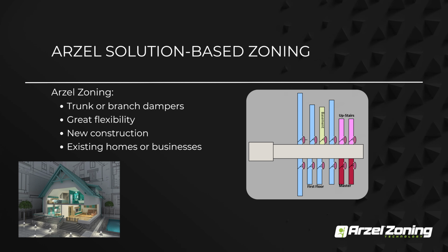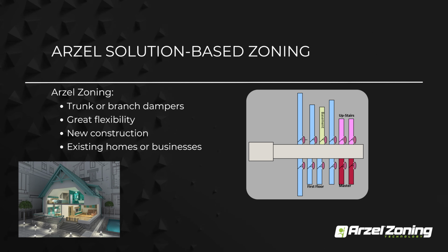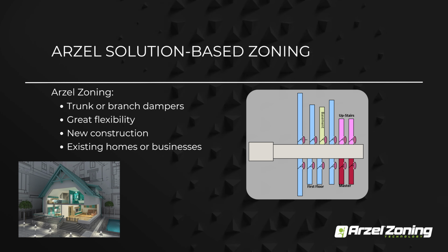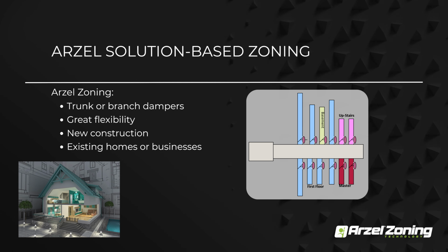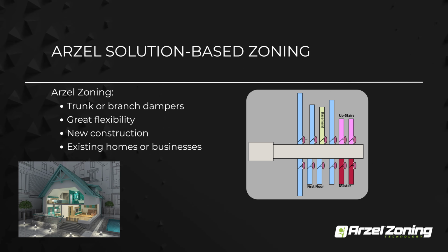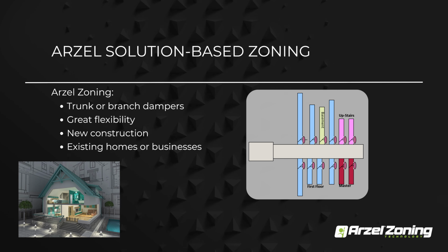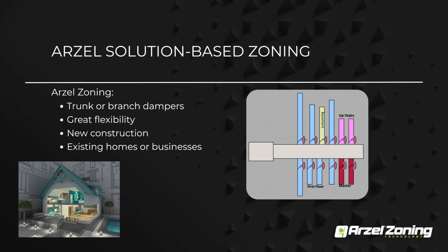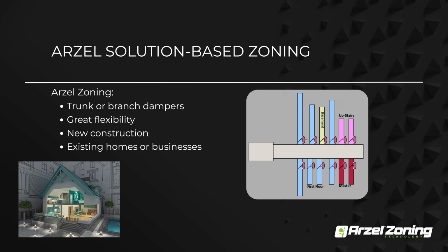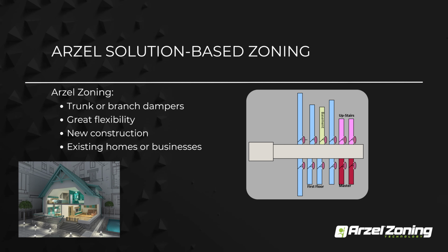So there's no redoing the ductwork. There's no adding new trunk lines. Really quick, really easy installation. And the really nice part is you can mix and match any of our dampers together. So if you have a mix of trunk and branch, some internal mount dampers, all of those can be added to the system. You don't need any extra transformers or anything, and we're able to support up to 35 dampers on one panel. If you ever have a case where you're going to do more than that 35 dampers, we can build a custom panel that would be able to do up to 70 dampers. Just give us a call at tech support if that's something that you need.